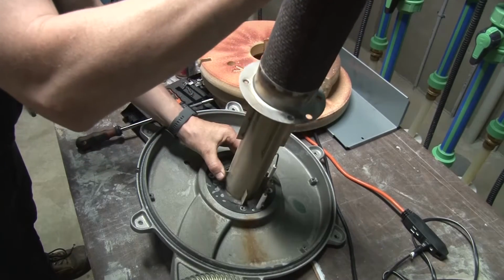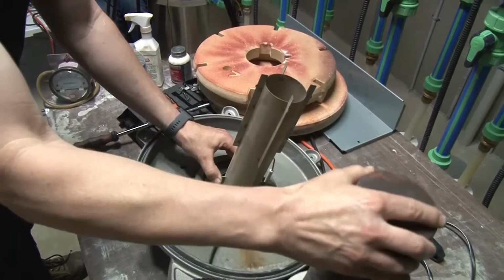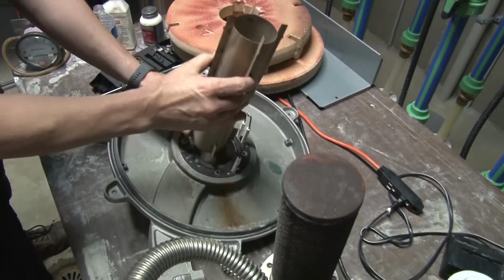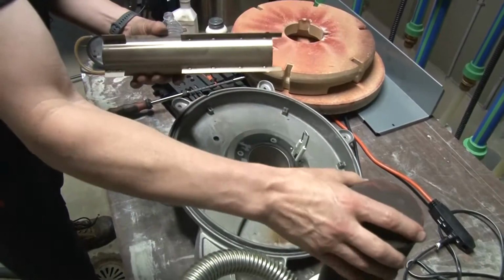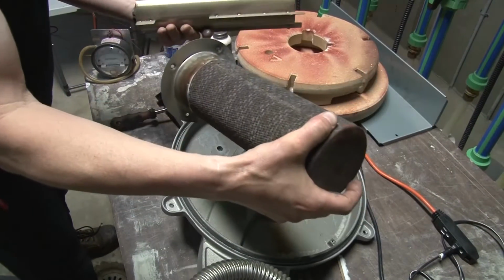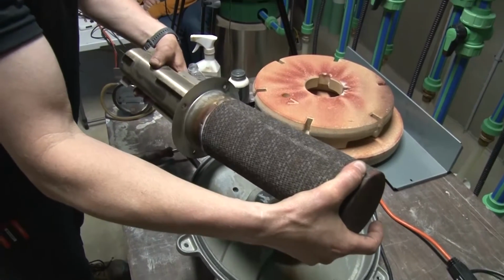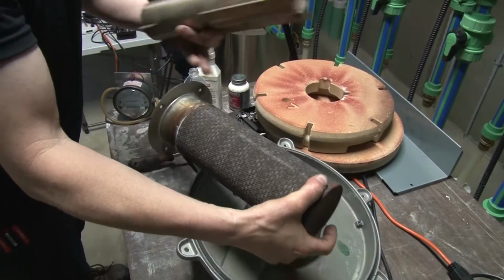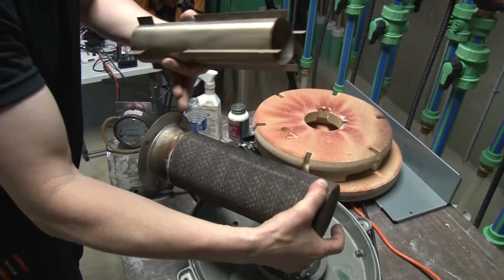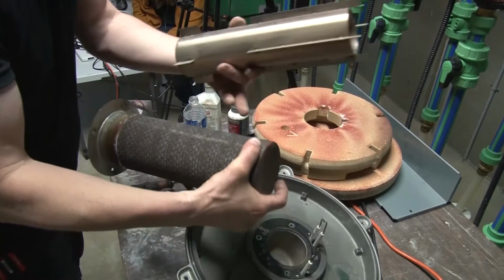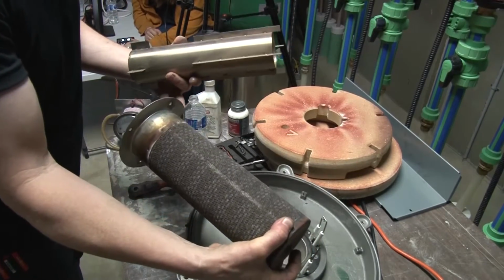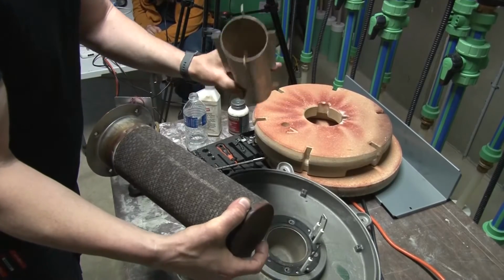You've got your burner tube, and on the other side of the burner tube is a turbulator. So basically what this does is it balances out. As we have that fuel and that air blending through here, it creates basically a pattern for that to go down the tube here. So we have a nice even distribution of that gas. So we have a nice even flame around the cylinder of the burner here. So we're just doing a little inspection here.